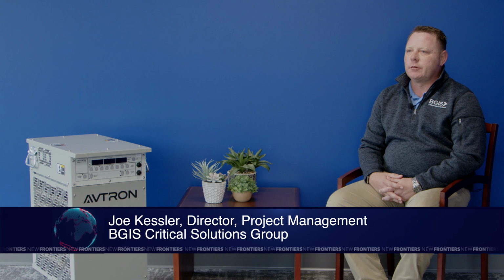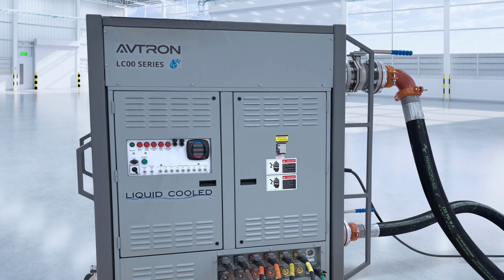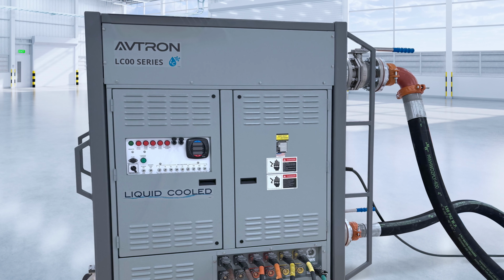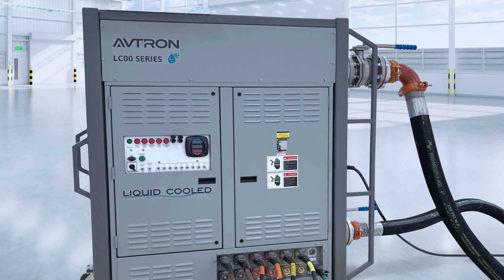BGIS Critical Solutions Group's core business is commissioning of data centers. We provide services from design to quality assurance to functional testing and integrated systems testing. The majority of that testing is validation that the equipment meets the design intent and reliability the customer requires. Since data centers are measured on capacity, it requires us to perform all of these functional tests at design rated load.